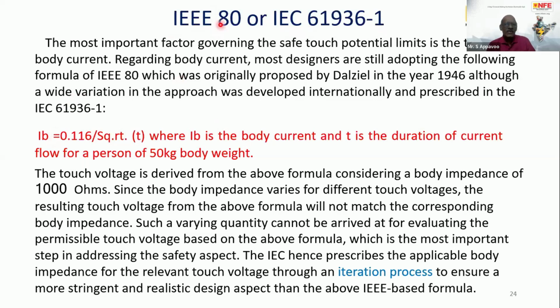So as per IEEE 80, this is the body current. I think this particular expression gives the first step in arriving at the touch potential. It is based on the body weight and a constant depending upon the fault clearance time. So this body current was defined somewhere in 1946 by one stalwart Dalziel in the US. Unfortunately, it assumes a constant 1,000 ohms, unlike the body resistance itself, which varies due to the application of different voltages. That is not taken into account.